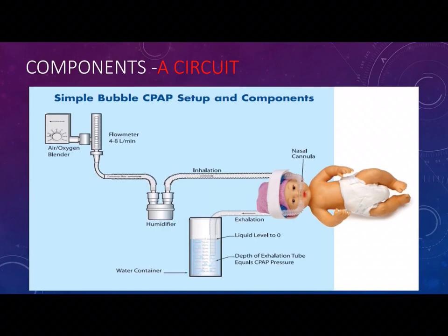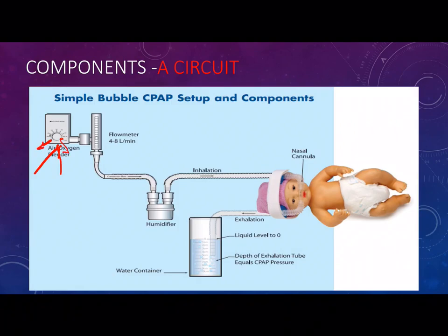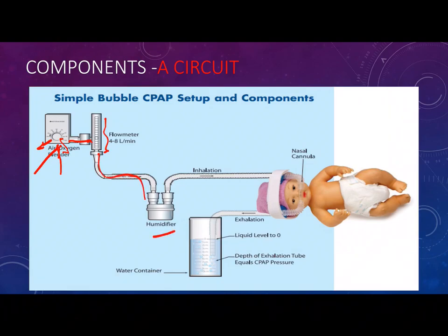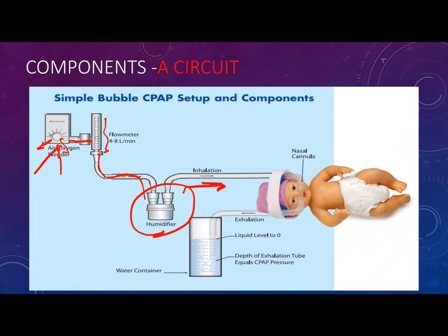Looking at the circuit: we have oxygen and air inlets going to the blender. The blender mixes oxygen and air to give us the target FiO2, starting from 21% up to 100% — though in practice we do not exceed 60% on CPAP. Then the flow meter controls how many liters to deliver to the baby, from 5 to 10 liters. From the flow meter, there is a connection to the humidifier, which warms and humidifies the gas, then sends it to the baby through the inspiratory limb, which usually has a water trap to collect any condensed water before it reaches the baby.